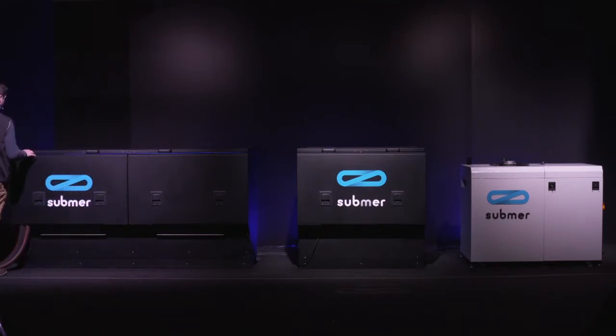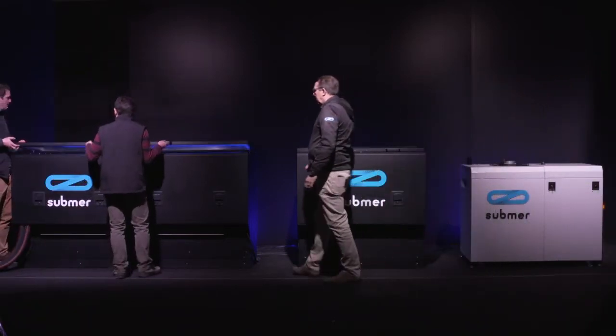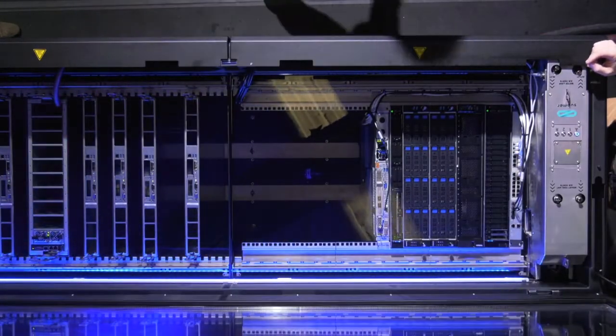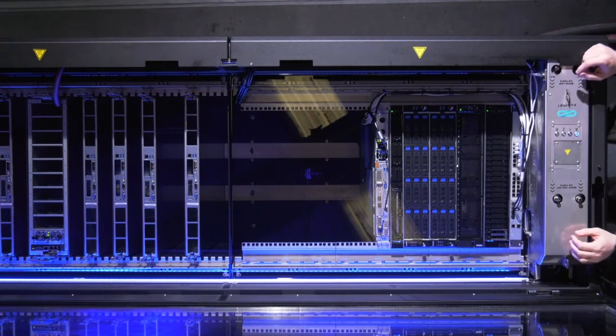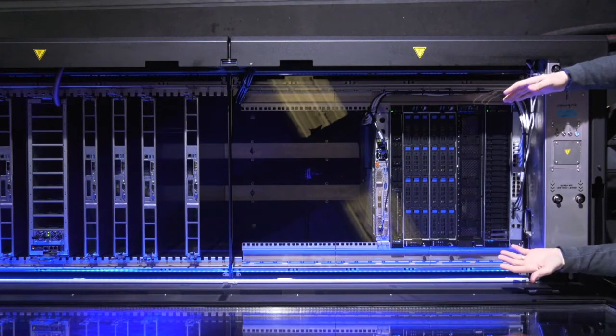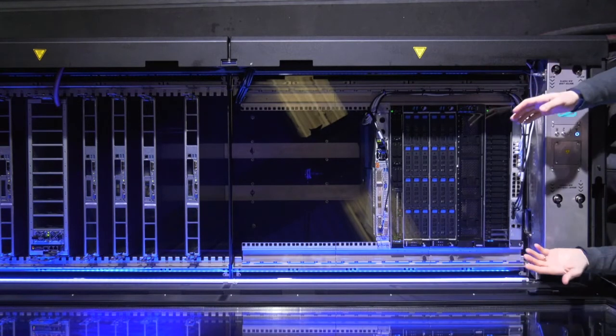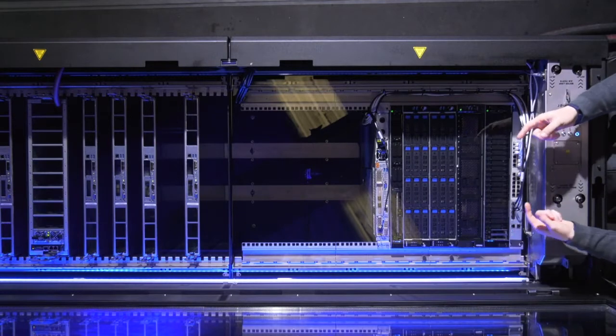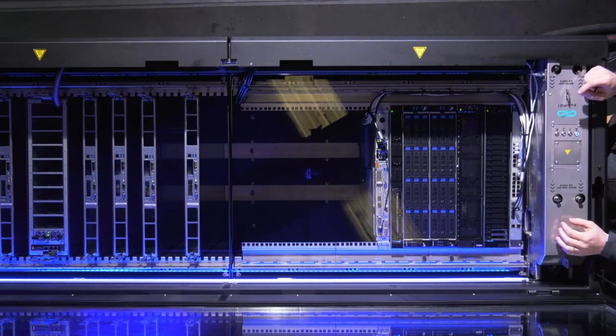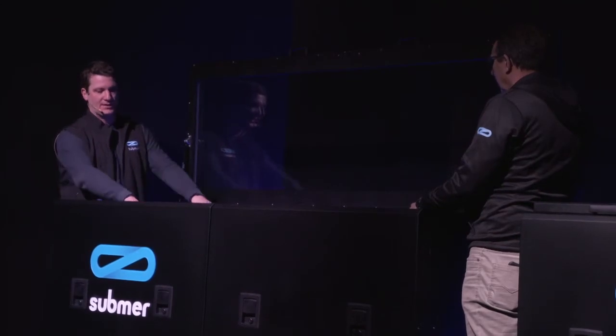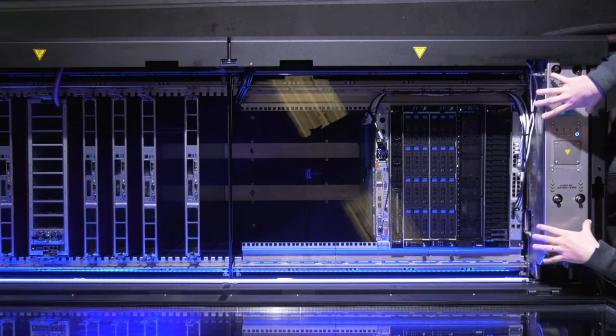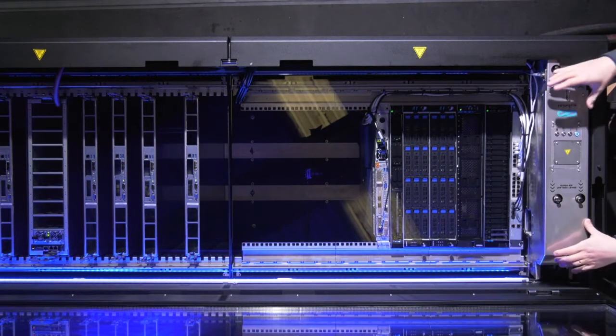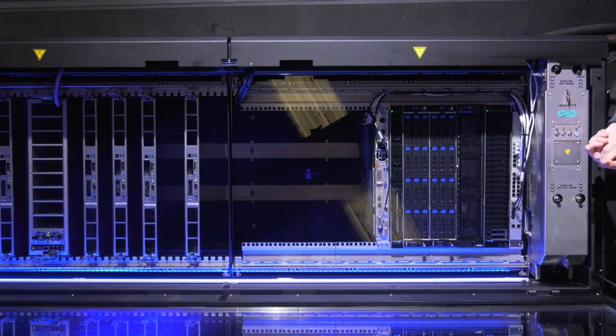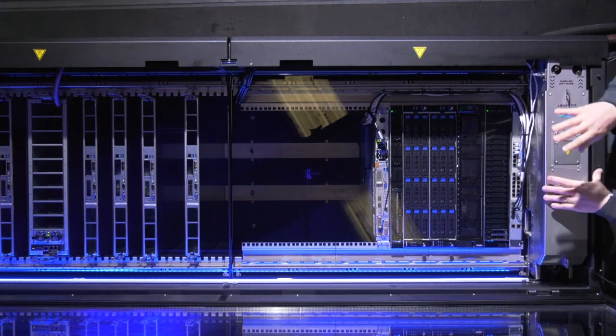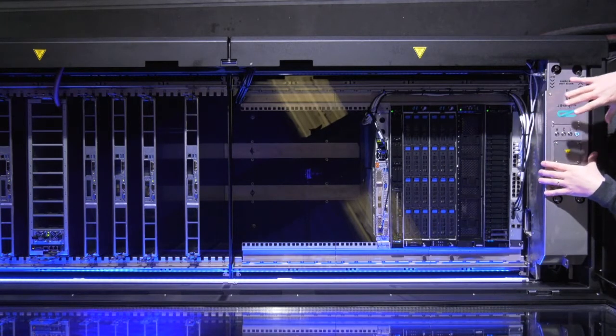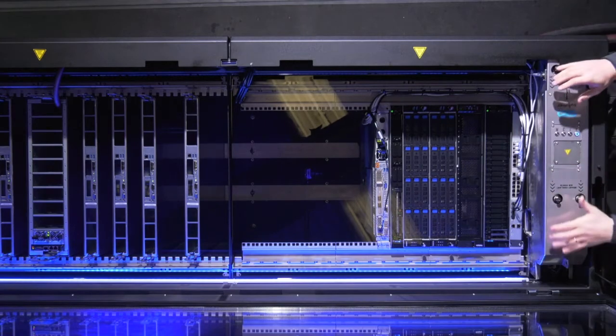And Edgar, if you can help me open the unit, and I'll showcase you what's in it and how it works. So what you'll see here is obviously it's a tank full of fluid. The way that the fluid is managed is by injecting the cold fluid at the bottom of the tank evenly along the tank. It flows gently through the IT hardware, and it's collected then again by the cooling distribution unit, which is the brains of the system. And the cooling distribution unit is designed to pump all that fluid through a heat exchanger which is inside of it and transfer all the heat to the facility water loop.